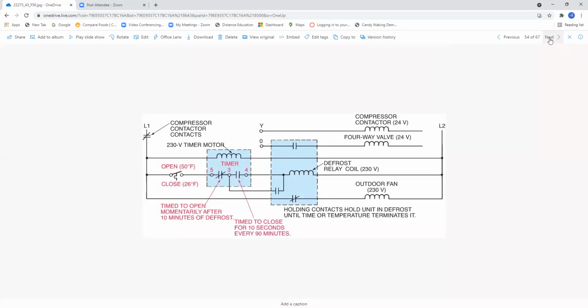We talked about this earlier, about the outdoor thermostat in conjunction with the timer in order to energize defrost. Typically the timer is designed to close for 10 seconds every 90 minutes of operation. And if this thermostat does not close, defrost will not come on. Simple as that.